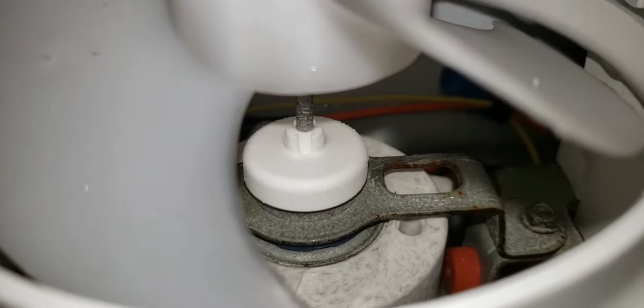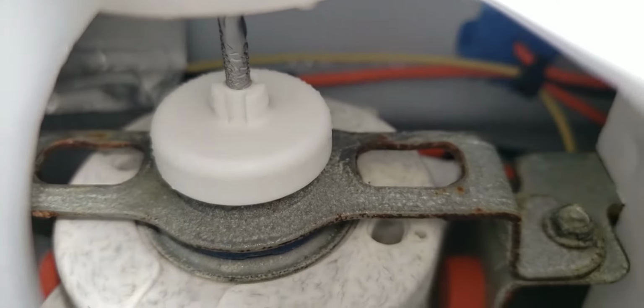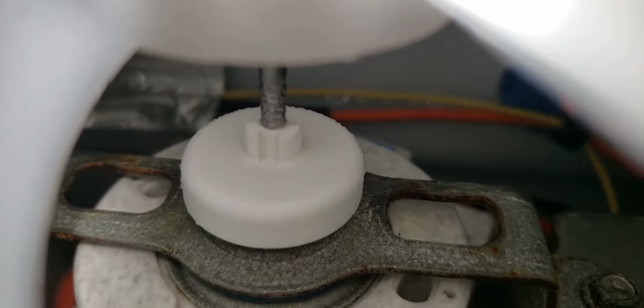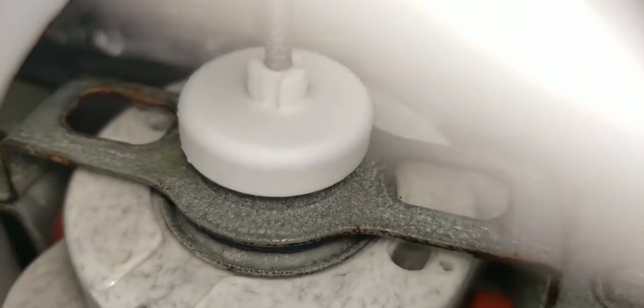The motor appears to look good. No ice buildup. So no damage in the seals would be the main concern. All else looks good. All conditions normal.